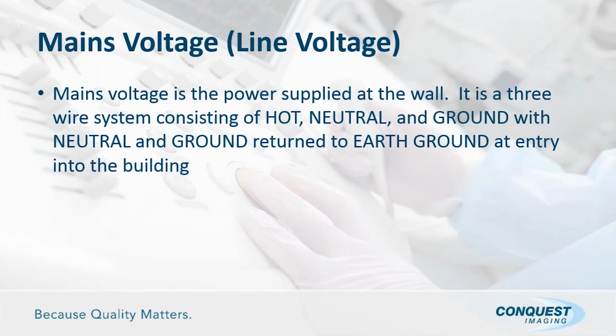Next thing we move on to is what we call mains voltage, and again, some manufacturers may refer to it as line voltage, source voltage. It just depends on what meter you're using. But mains voltage is basically the power supplied at the wall. In the U.S. and as far as NFPA 99 is concerned, it's a 3-wire system consisting of hot, neutral, and ground. And neutral and ground are returned to the earth ground at entry into the building. And that's why we can't determine the reverse of the two, because they're essentially the same.